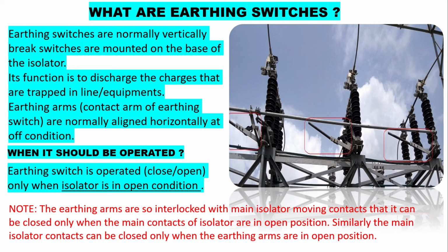Now comes when and how it should be operated. Again, only when isolators are in open condition can the earth switch be operated, that is, perform close or open operations. Note that the earthing switches are interlocked so that they will operate only when isolators are in open condition, and the interlocking for the isolator is that it can be closed only when earth switches are in open condition.